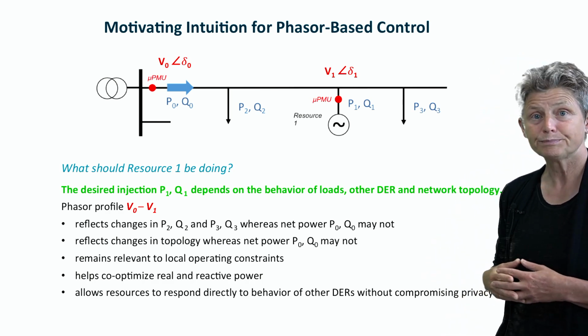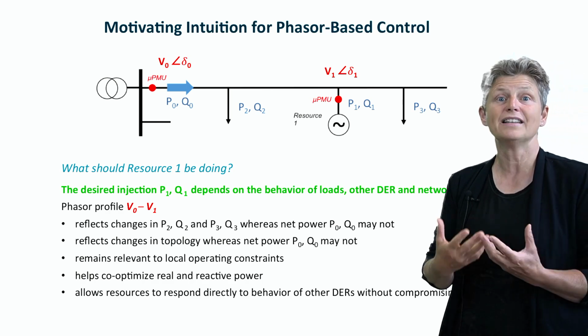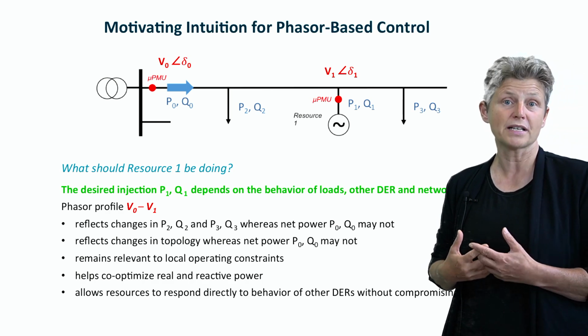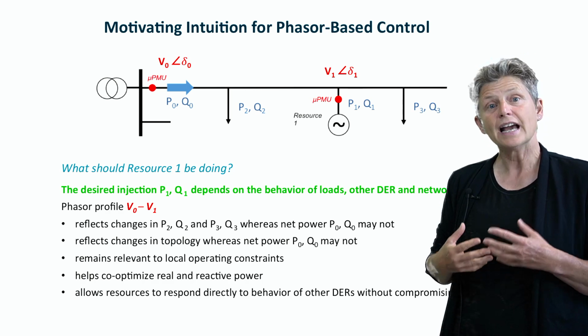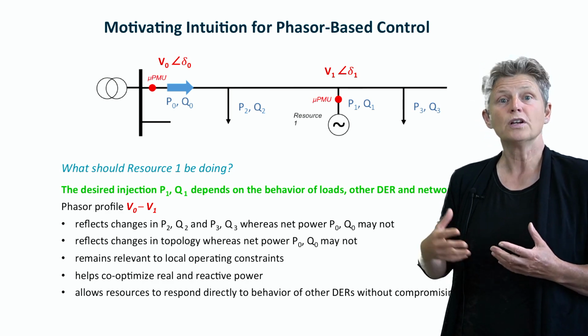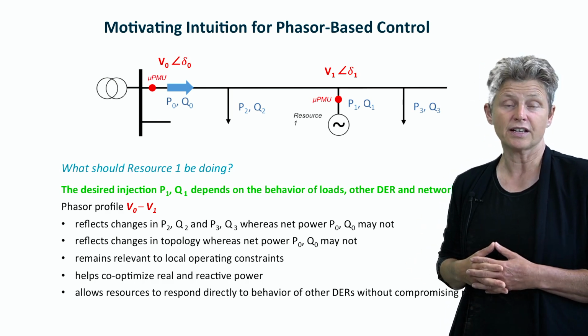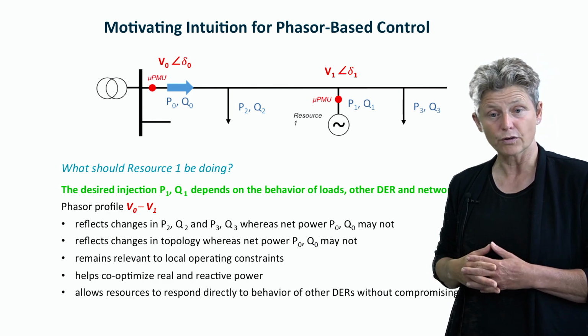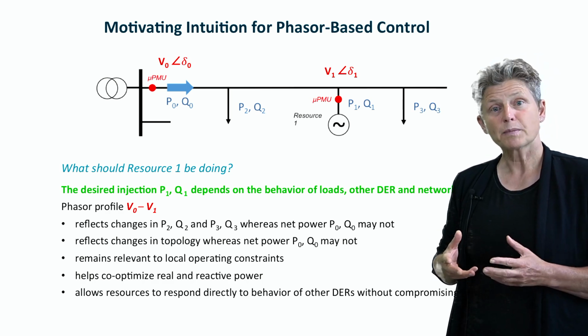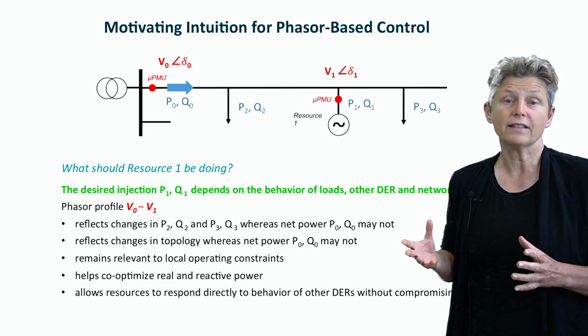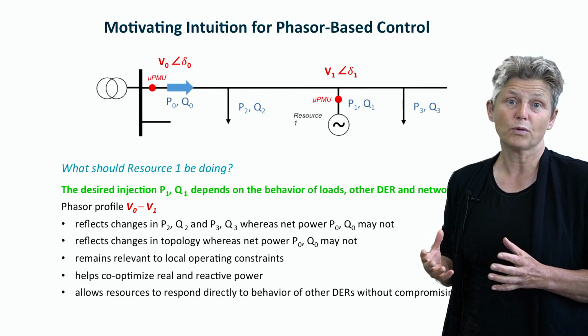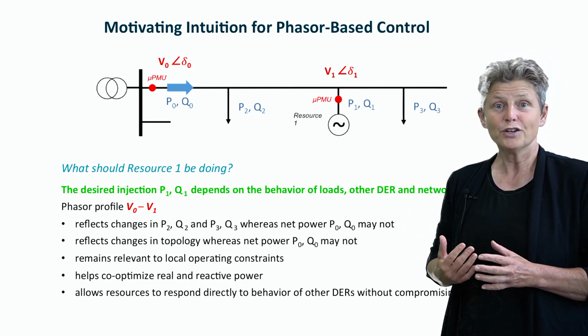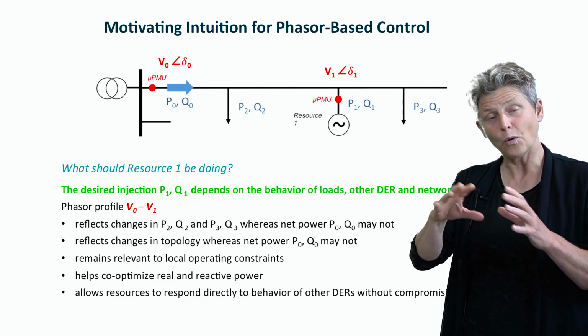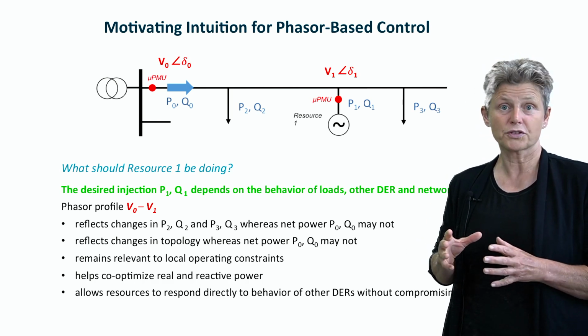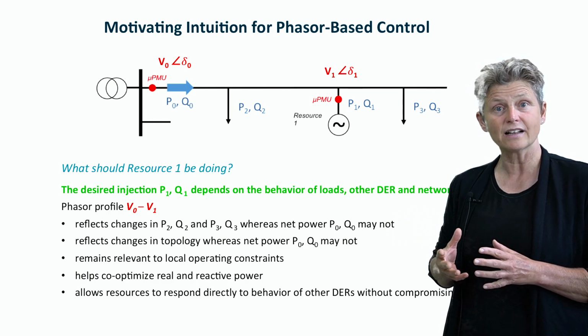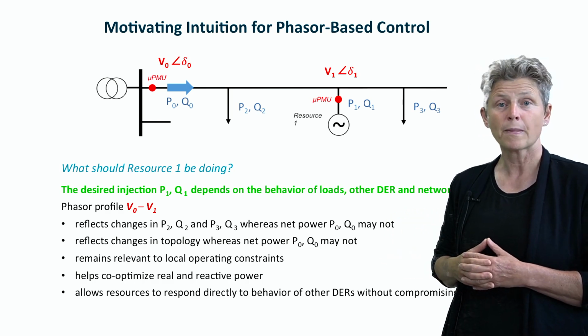Now, this is in a sense similar to what's already done for volt-var control, for reactive power management, adjusting to real-time measurements of the voltage and correcting the voltage magnitude by increasing or decreasing reactive power output at the inverter. In phasor-based control, we augment that, or integrate it with real power control, so that we have this whole integrated control schema for both voltage magnitude and angle, and both real and reactive power.